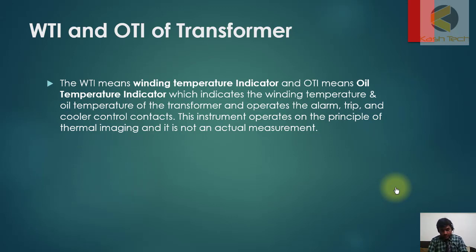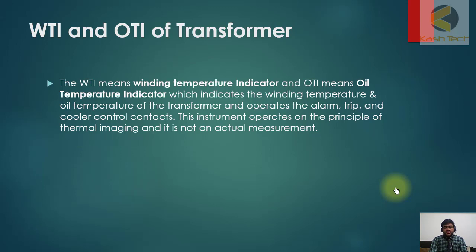There are fans installed in transformers for cooling. If temperature increases beyond a certain limit, fan group one will turn on. If temperature rises further, fan group two will turn on. At the third level, an alarm will be initiated, and at the fourth level, tripping is initiated. This is how winding temperature and oil temperature indicators work.